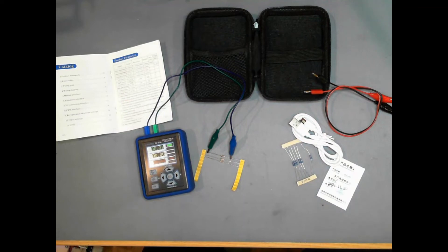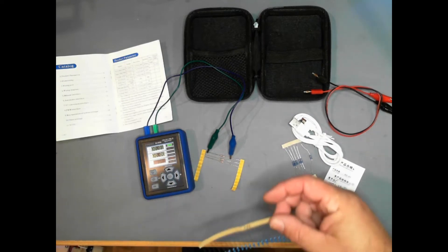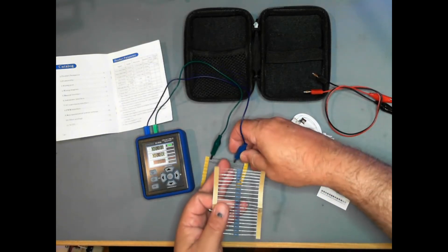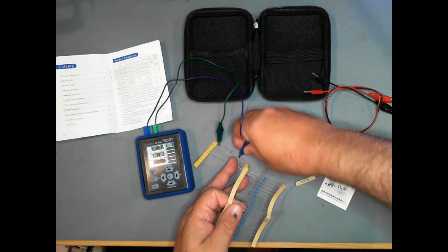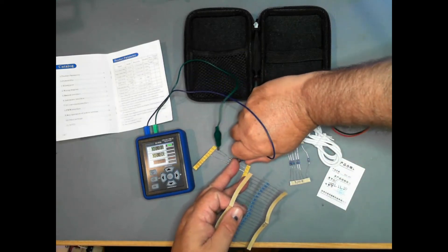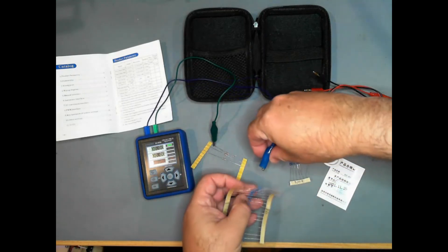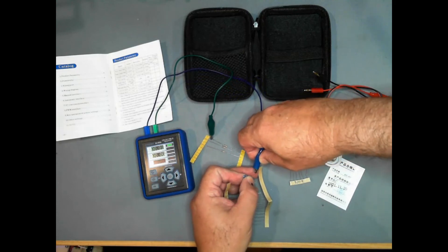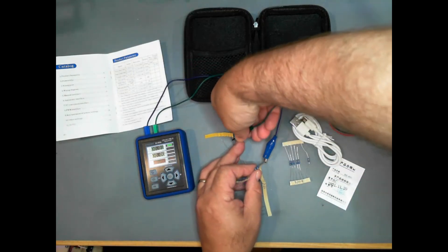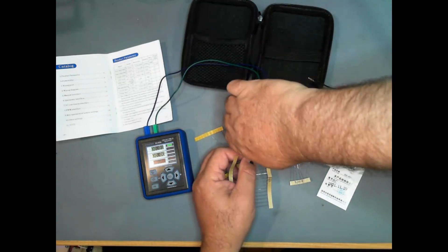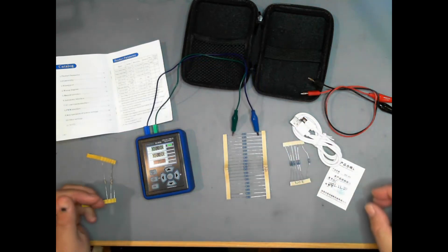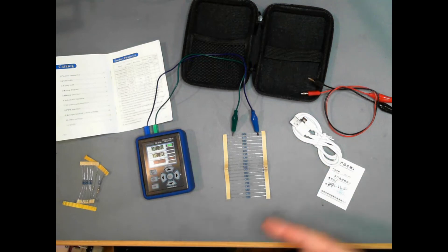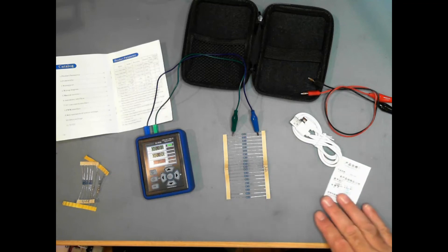What I need is a better resistor. So that's supposed to be a 1k ohm resistor. If I connect this up to 1k ohm, maybe not the best one, but it is showing 21 milliamps flowing. The maximum current it will pass through and read is 24 milliamp, so it's basically doing what we're expecting it to do. If I put a larger resistor on, we should get a lower current rate. This is 5.6k ohm, and that's 4.04 milliamp. So with a 24 volt output, if we do the math, we'll get around about the 4 milliamp range which is what we're getting.